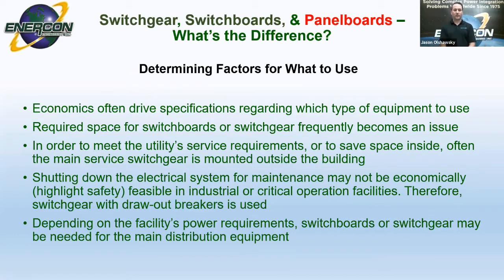Shutting down the electrical system for maintenance may not be economically feasible in industrial critical operation facilities. Therefore, switchgear with draw-out breakers are used. What makes draw-out breakers much more widely used is in case of a breaker failure, if a breaker goes bad. If it's a fixed mounted breaker, the copper bus, either the run backs or the risers, are going to be connected directly to the breaker. So if you had a breaker go bad that was fixed mounted, you'd have to completely isolate that bus in order to get in there, disconnect the breaker itself from the copper bus, and then remove it to replace.